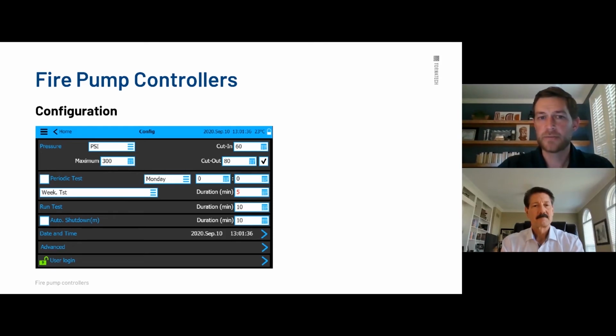This is where you can also enable the periodic test. The periodic test is always active as long as that button on the front is functional. But that's where you would have to manually come in and do the periodic test. So you manually come in and push it, just like a manual start where you're just pushing the green button and it's a manual start. When you come in and manually press that test button, that's where it will open up the valve, drain a little bit of water, and do a test.